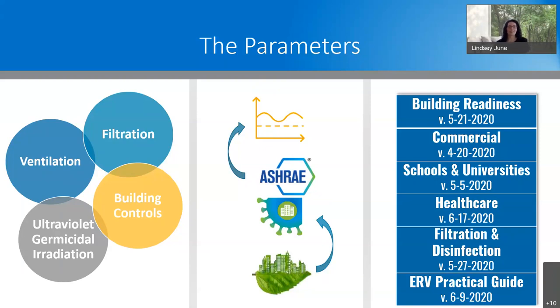The second package was deemed the energy efficiency package, and this consisted of evaluating strategies that would enable a more energy efficient solution while maintaining the IAQ effectiveness of the ASHRAE package or of a deemed IAQ target. So the results of the package evaluations needed to be presented in comparison to specific baselines. The ASHRAE package needed to be compared to the pre-COVID building operation energy use baseline, and then the energy efficiency package needed to be compared to the ASHRAE package of measures energy use baseline. Final note is that 100% occupancy was assumed for these projects, so the results could enable buildings to resume prior occupancy levels.